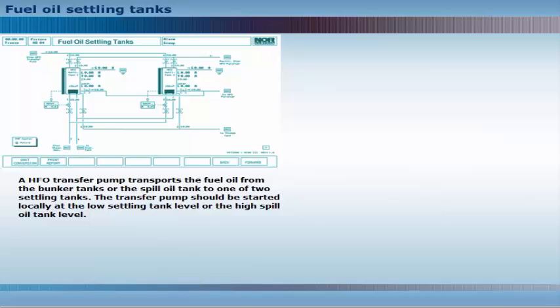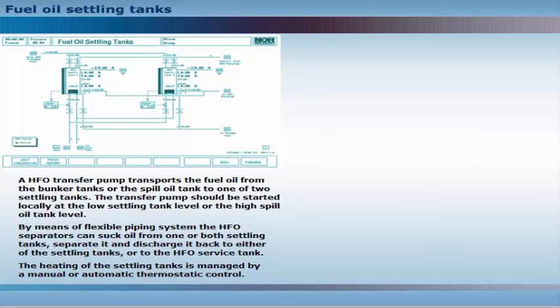The transfer pump should be started locally at the low settling tank level, or the high spill oil tank level. By means of a flexible piping system, the heavy fuel oil separators can suck oil from one or both settling tanks, separate it, and discharge it back to either of the settling tanks or to the heavy fuel oil service tank.